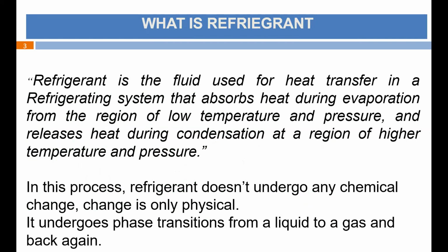Fluid, as you know, can be in the liquid stage or vapor stage. It is used for heat transfer in the refrigeration system: it absorbs heat during the evaporation process from the region of low temperature and pressure and releases the heat during condensation at a region of higher temperature and pressure. If you recall the refrigeration cycle, there is an evaporation process in which the refrigerant absorbs the heat from the surroundings, and the heat is discharged in the condensation process at higher temperature, either into a secondary refrigerant or into air. So this is the basic of refrigerant.